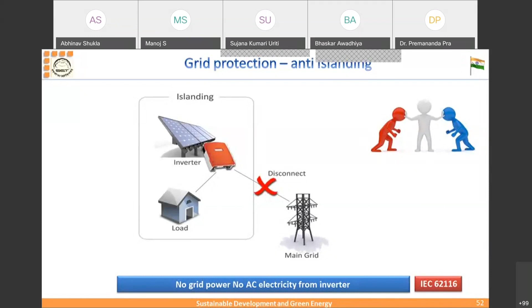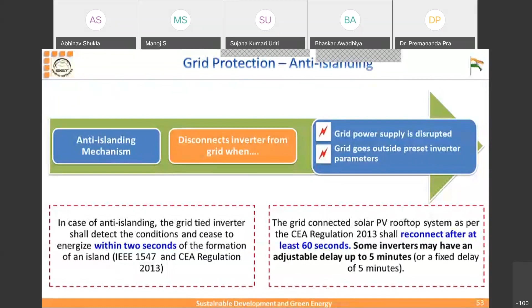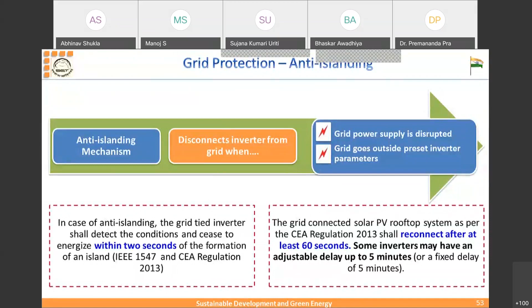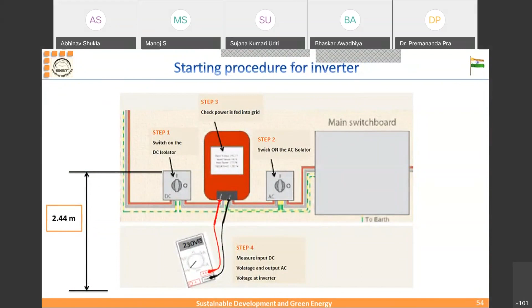So this is the further explanation of anti-islanding. In anti-islanding, the time limit is 2 seconds. So before 2 seconds it will disconnect. The disconnection time is generally 0.2 seconds, but within 2 seconds it will get de-energized, and if the reference becomes available, it will take another 60 seconds and then it will start. This is as per the guidelines of IEEE 1547, and this is highly important. And the isolator switch cannot be more than 2.44 meters, because the highest point of the isolator, either the DC isolator or the AC isolator, should not be more than that as per the guidelines. You can read this in all the policies, and it is as per the grid codes.